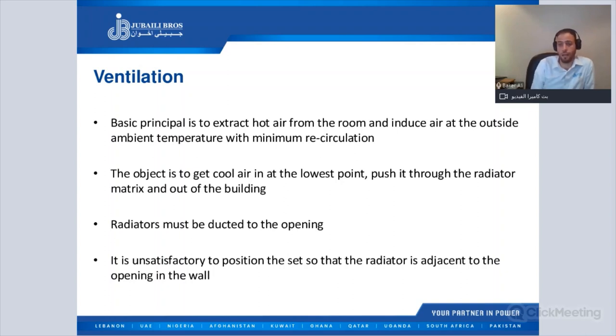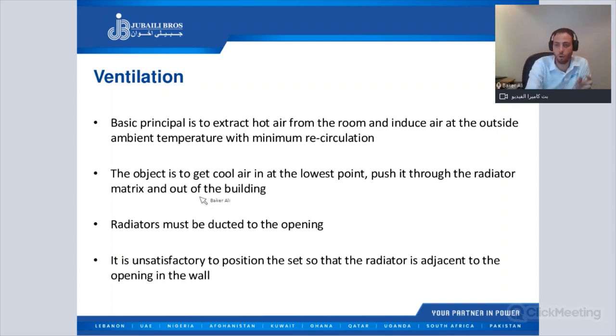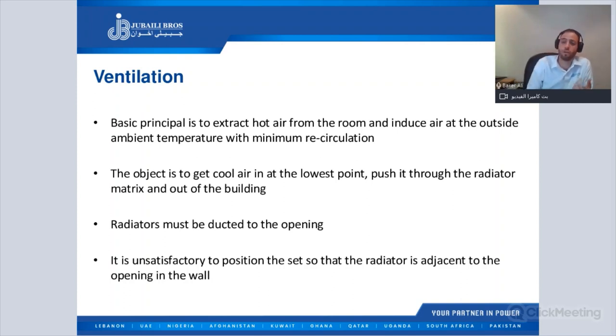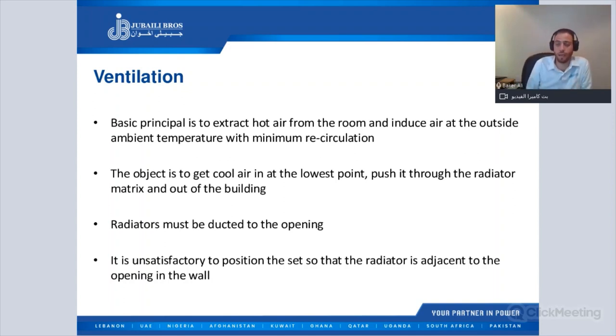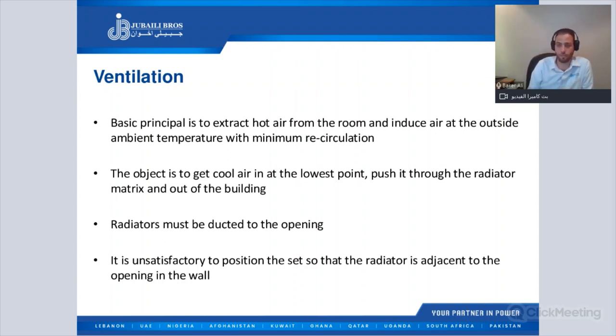The radiator must be connected to the outlet opening with a duct to take the hot air from the radiator to outside the room. Some people attach the radiator directly to the opening, which is not acceptable. A small gap between the opening and the radiator will cause hot air recirculation inside the room and airflow restriction. We must keep a minimum distance of one meter between the radiator and the opening and connect ductwork over that distance.